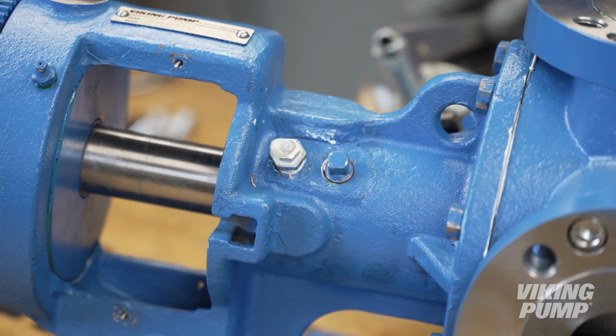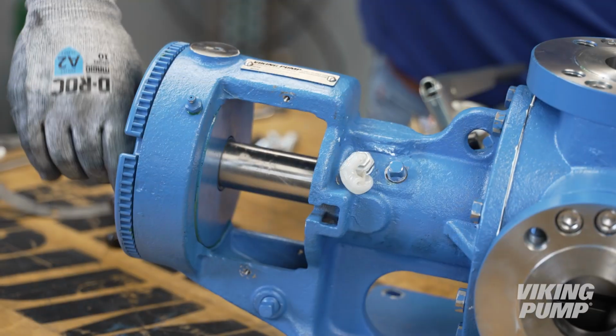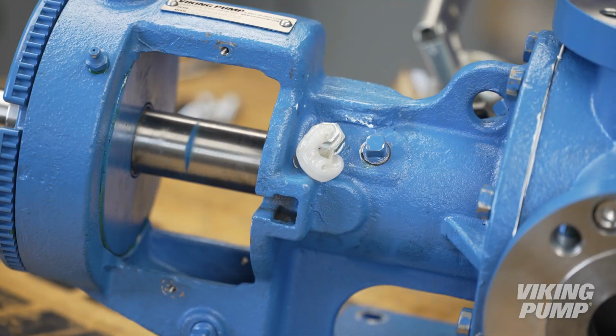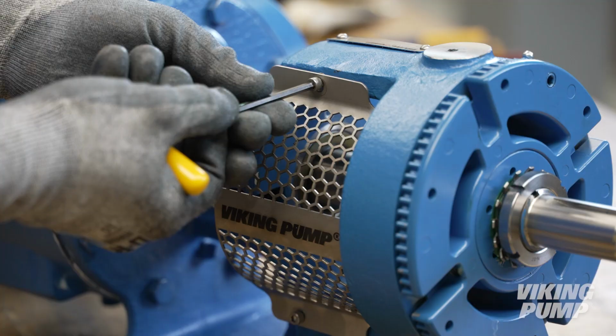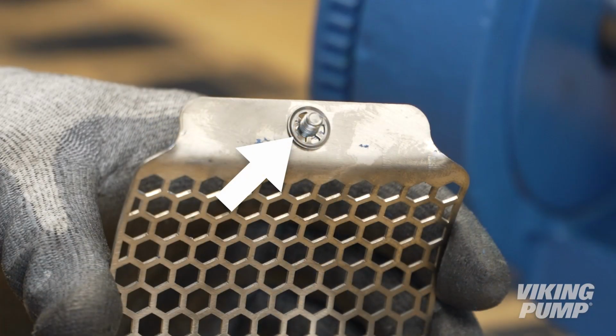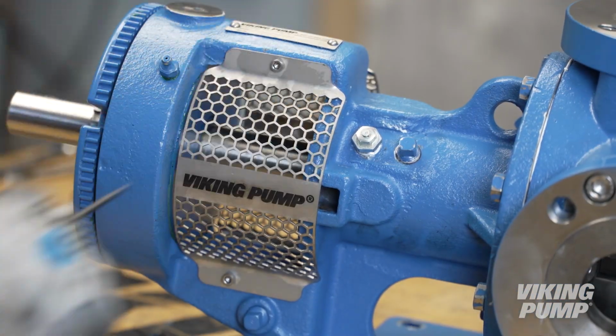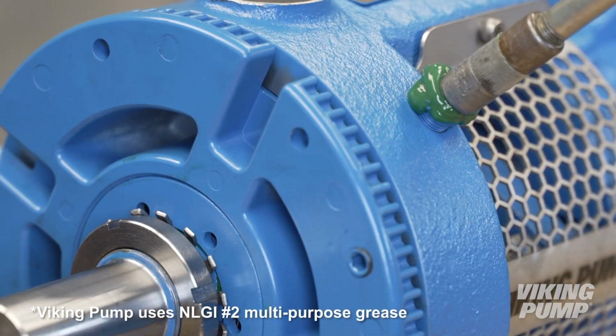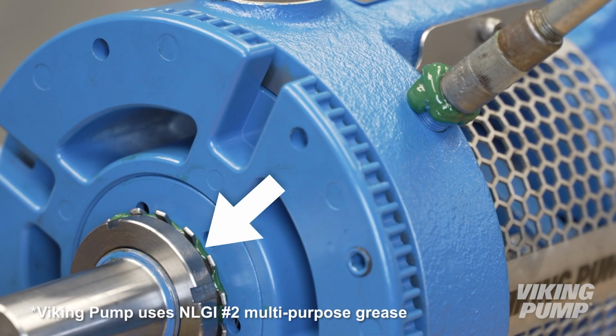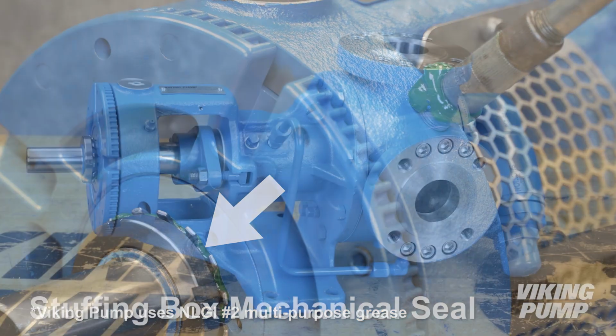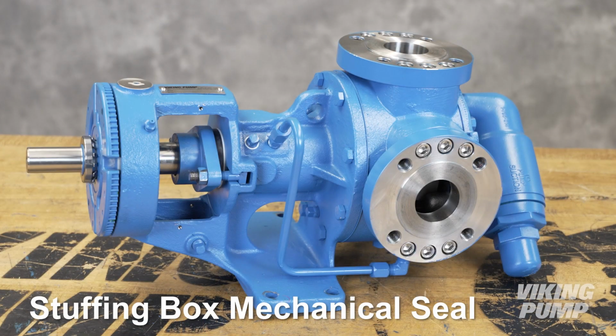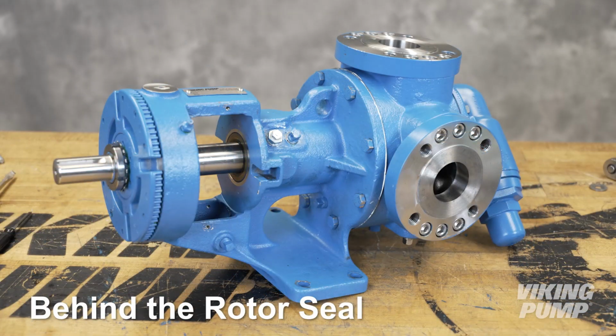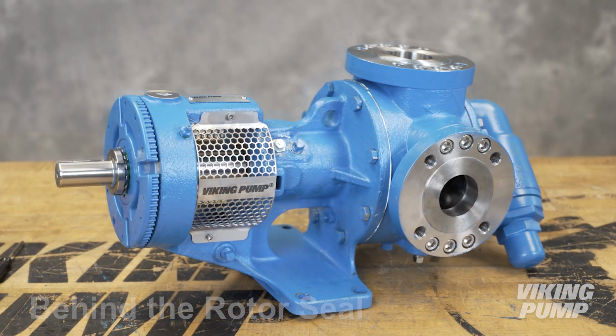Next, grease the bracket with application-appropriate grease. Rotate the shaft while greasing and continue to fill until grease is released through the pressure relief fitting. Reinstall the window guards. Ensure that the retaining washer is placed between the guard and bracket faces. Finally, grease the bearing housing until grease begins to appear around the lock washer. Your pump has now been converted from a stuffing box component mechanical seal to a behind the rotor seal and is ready to be put back into service.